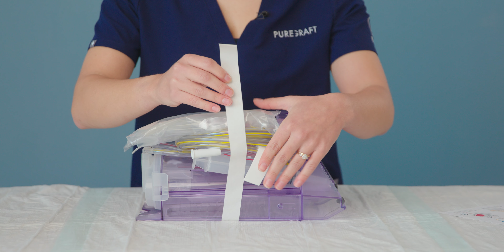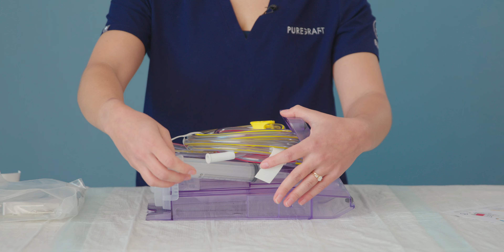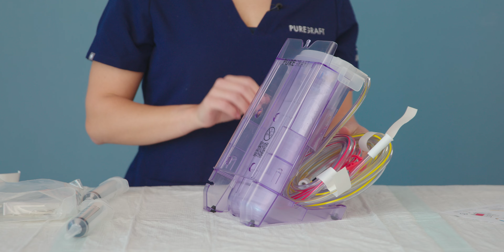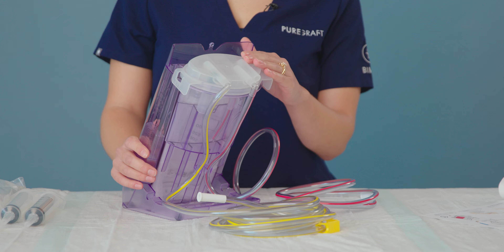Now we will set up the sink device for harvesting. Remove the cohesive tape band from around the sink device. Set aside the accessory pouch and catheter-tip syringes. Stand the sink device upright. Remove the cohesive tape loops from the tubing coils. The tubing is already pressed into the tube holders on the back of the sink device. Now press the yellow patient tubing into the tube holder on the side of the device and the red patient tubing into the tube holder on the other side. This ensures that the sink remains upright and stable while harvesting.